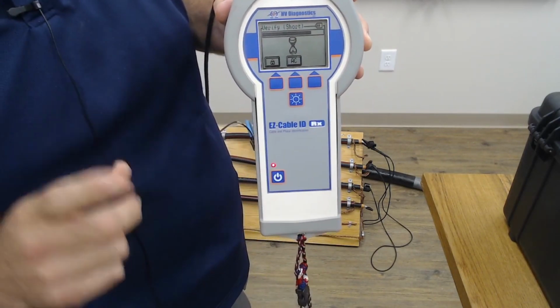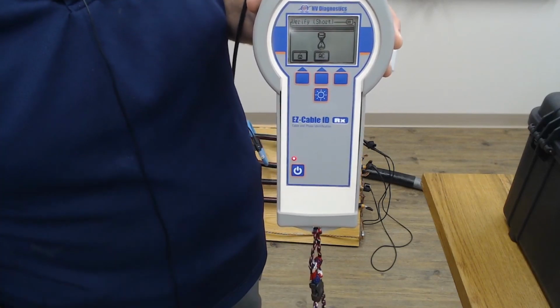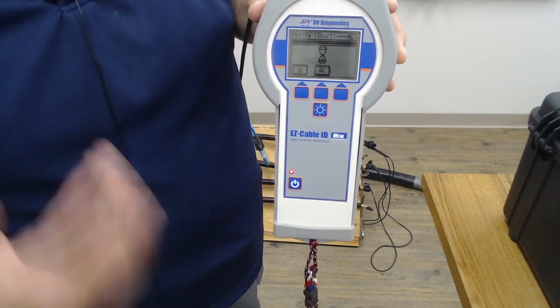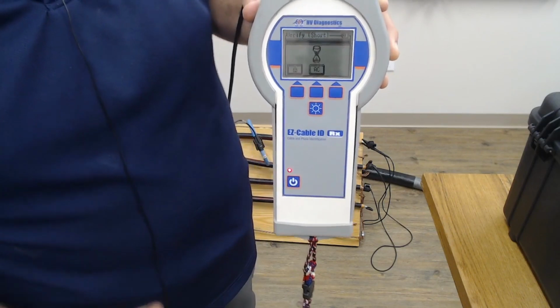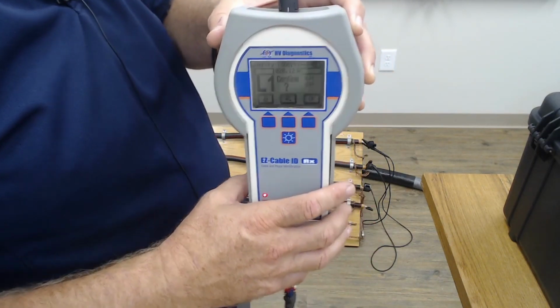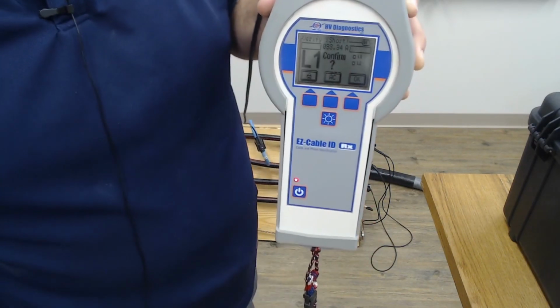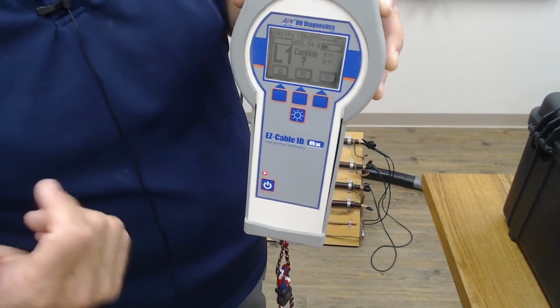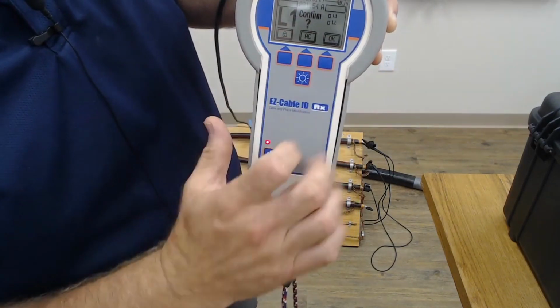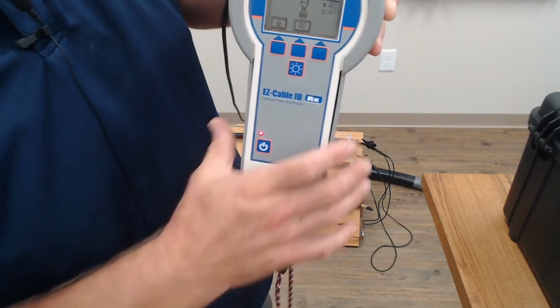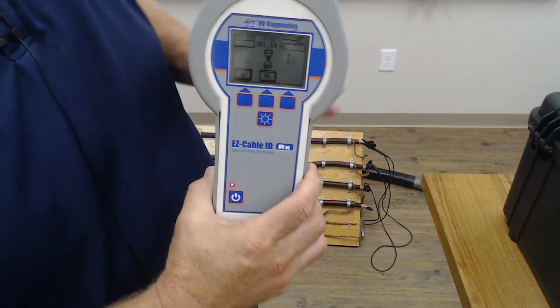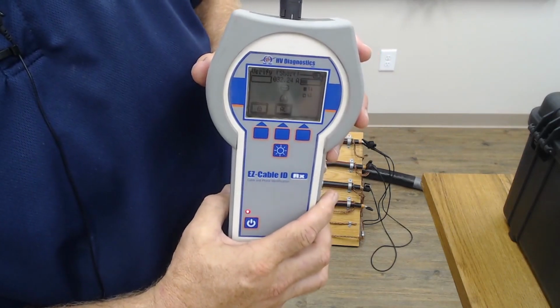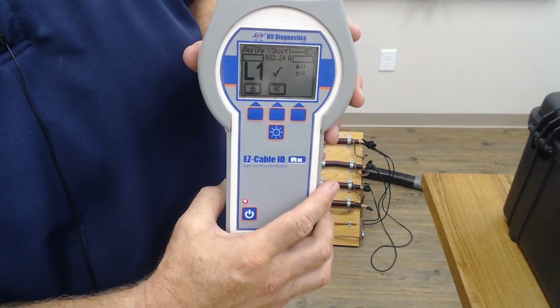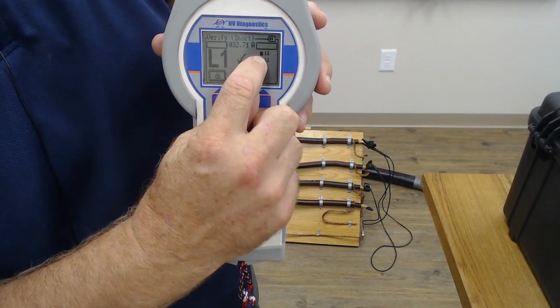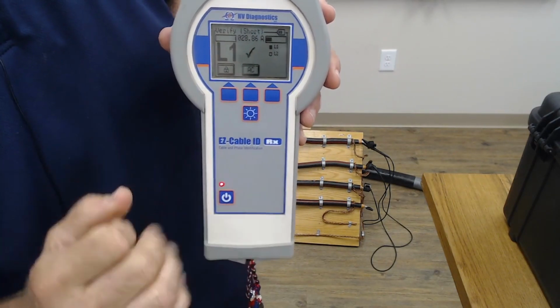In other words, it's asking you as a user to confirm that you are in fact on your L1 phase. And you go back and you look at where your transmitter is connected. You make sure the breaker nameplate says A phase, or the riser says this is A phase. And you see L1 question mark, and you say, yes, that is correct. There we go. L1 is correct, and your little check mark is in L1 there too, saying it's captured that.